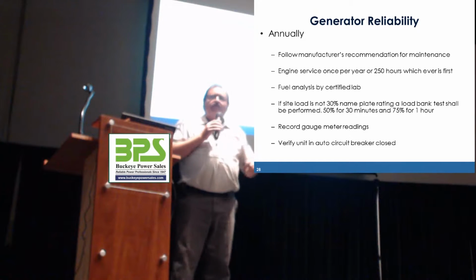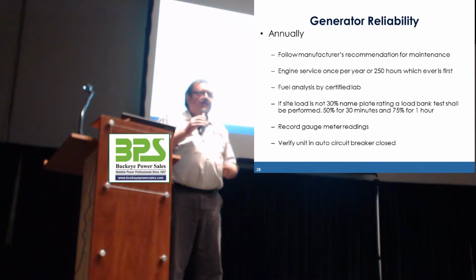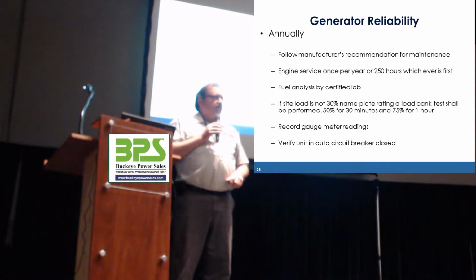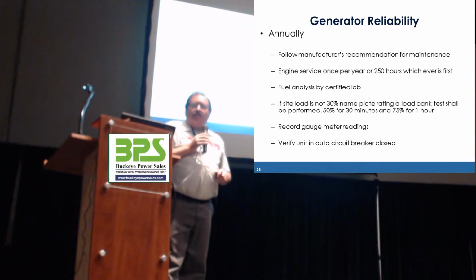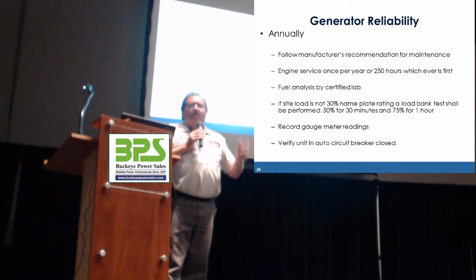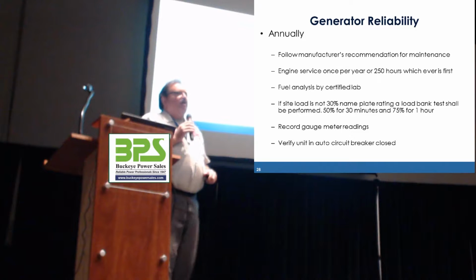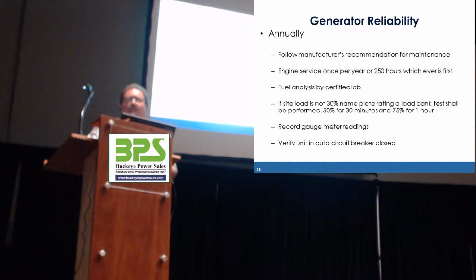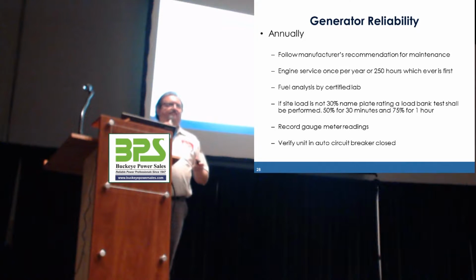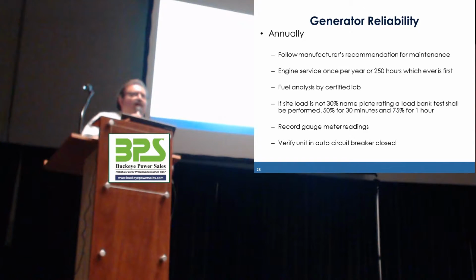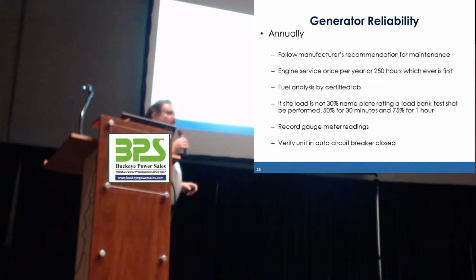And it's being enforced by the Ohio Department of Health that you have to add more load to your generator so that you meet that 30% nameplate, even though newer versions of the code allow you to just use whatever load there is on the natural gas. But chances are none of you here have spark-ignited units, correct? Everybody's diesel? Okay. So if you don't have that 30%, then we need to load bank it.